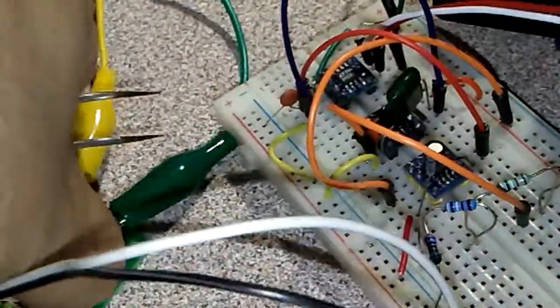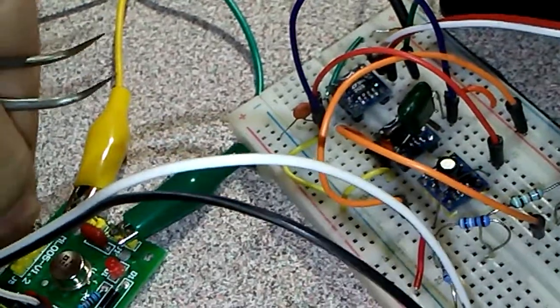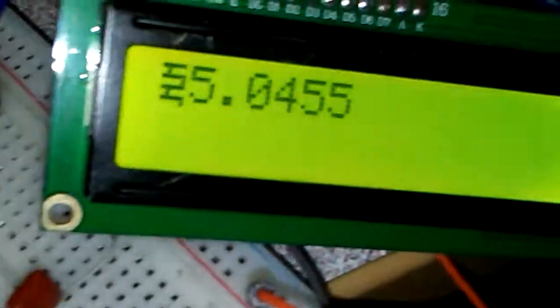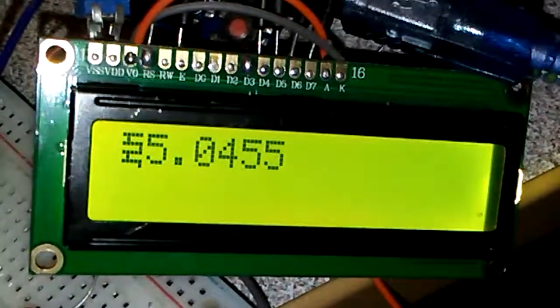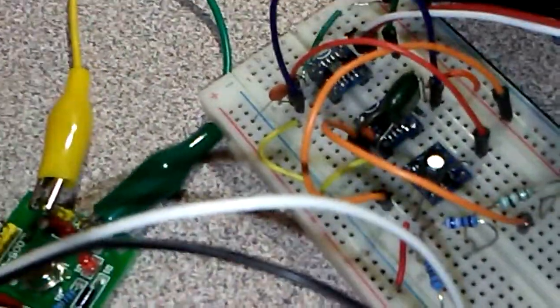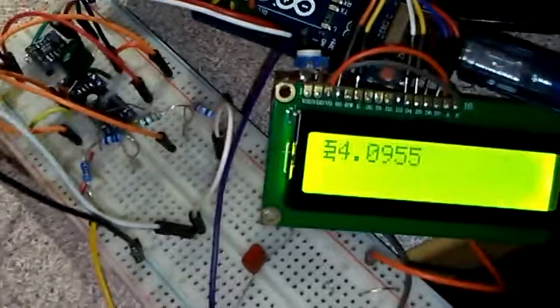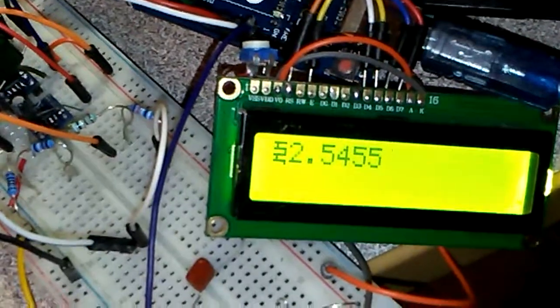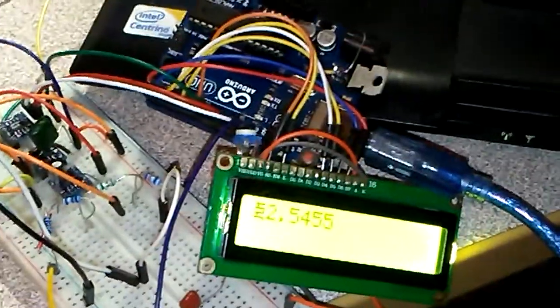The next setting to change is 5 volts — you can see it reads 5.0455. And the last test is 2.5 volts — you can see it reads 2.5455, which is very close to the readings from high-quality Keysight and Fluke multimeters.